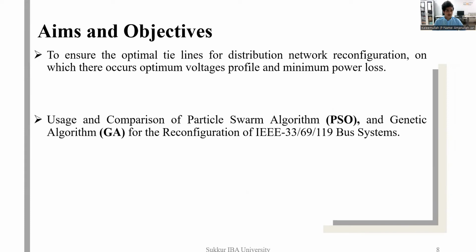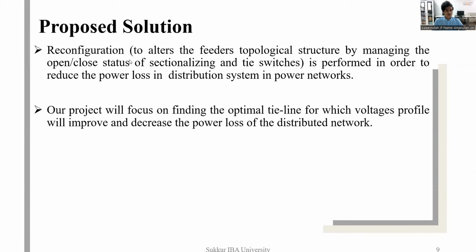These are the aims and objectives of our project: to ensure the optimal tie lines for distribution network reconfiguration, with optimum voltage profile and minimum power losses. Also, the usage and comparison of PSO, particle swarm optimization, and genetic algorithm for the reconfiguration of the IEEE 33, 69 and 119 bus systems. So, our proposed solution is reconfiguration, which means altering the feeder's topological structure by managing the open-closed status of sectionalizing and tie switches, in order to reduce the power losses in the distribution system and power networks. Our project will focus on finding the optimal tie lines for which the voltage profile will improve and the power losses of the distribution network will decrease.